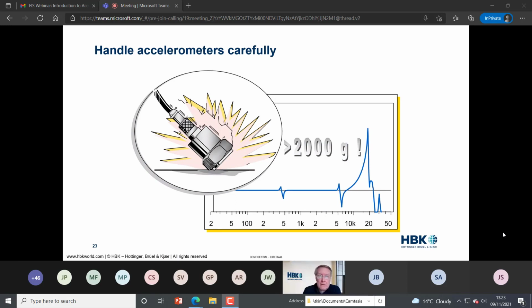2000 G sounds like a very large amount of acceleration. If you drop an accelerometer from tabletop height, let's say, onto a hard concrete floor, then it is perfectly feasible to get this sort of shock level, which will potentially damage the crystal inside the accelerometer. The sad thing about this is that you will not necessarily be aware that damage has happened. If it's really bad damage, then you might actually hear pieces shaking within the accelerometer. But if it's just marginal, you could end up with a frequency response such as shown here, which will only be detected by a full calibration.